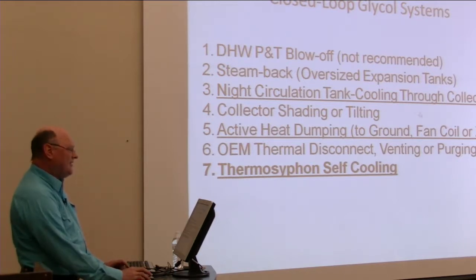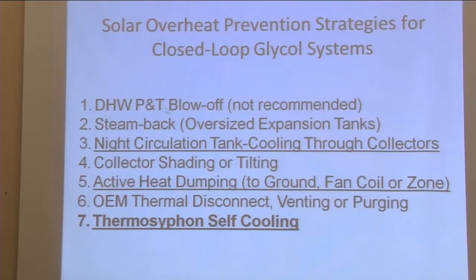Some of them, like the first one, is not recommended. That's sort of a last resort, where you put all the heat into a domestic hot water tank and it gets so hot that the pressure relief valve blows off. Well, yeah, that's an overheat protection because cold water comes into the tank to cool it, but you've just lost a lot of water down the drain. So not recommended. But the rest of these things are used all the time in different heating systems.